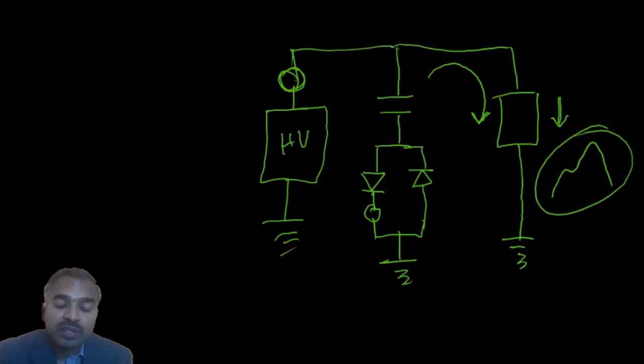So to avoid this, it can be minimized by connecting a resistor in series, a damping resistor, between the test object and the measuring circuit, which is basically a capacitor. That's the reason discharges can occur in the test object. Pre-discharges will modify the voltage waveform a little bit if not controlled using a damping resistor. So this can be addressed by connecting an appropriate damping resistor.